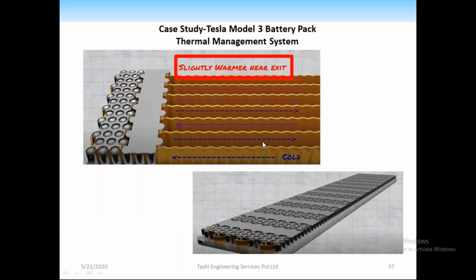Tesla uses cold coil where all the channels are in series. So the fluid comes back and forth like a snake, and here it becomes hot. What will happen is cells situated here will be slightly warmer than cells situated there. We don't want that, because intercell temperature distribution will result in cell imbalances, so the degradation of the cells won't be equal.